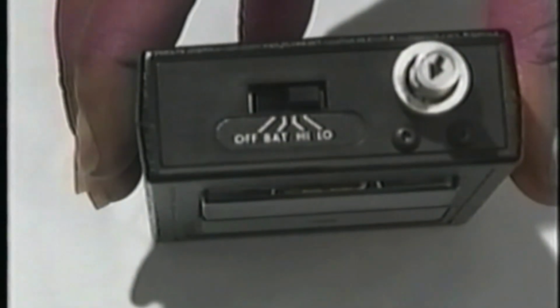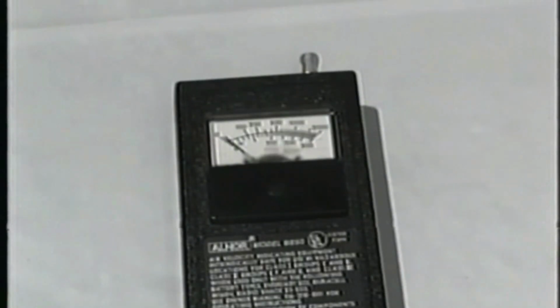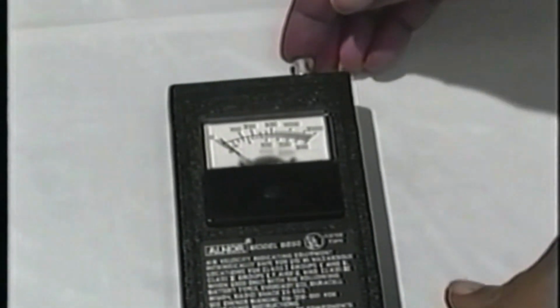For the electrical zero adjustment, first remove the cover plate. Then make sure a fresh battery is installed and turn the instrument to the low position. Be sure that the probe has been retracted into the case to prevent any airflow, and turn the zero adjustment screw on the left-hand side of the unit until the meter needle lines up with the zero division.